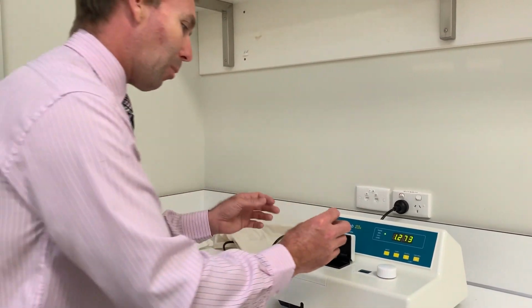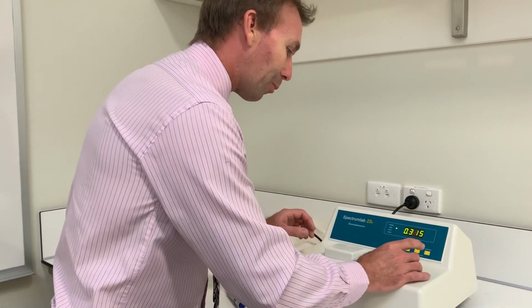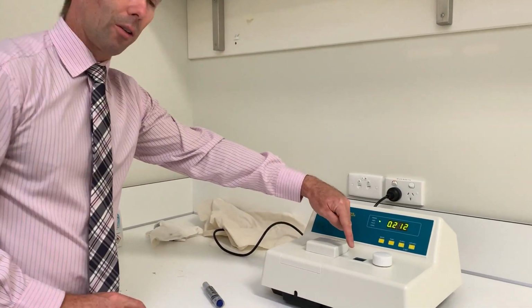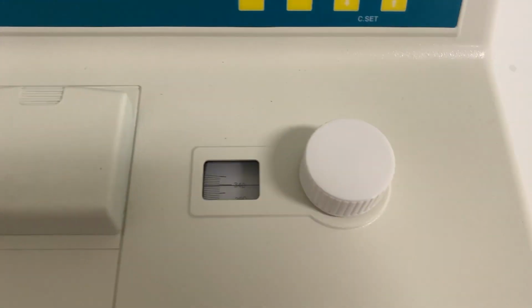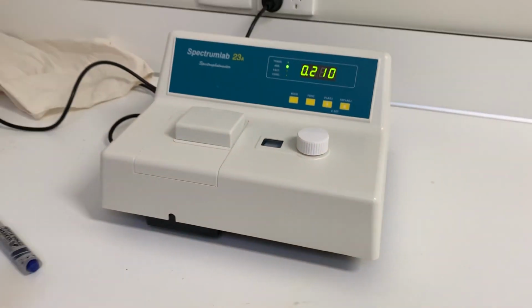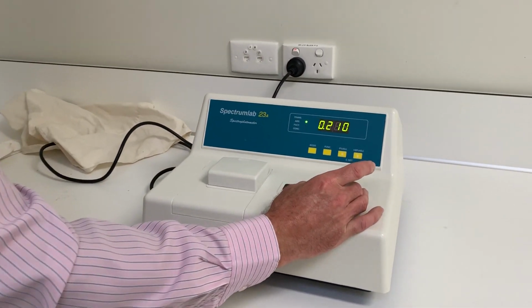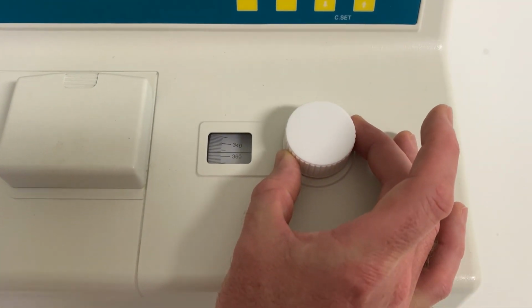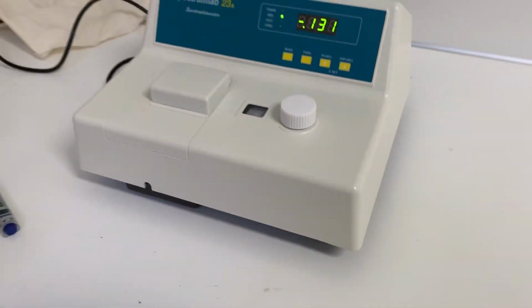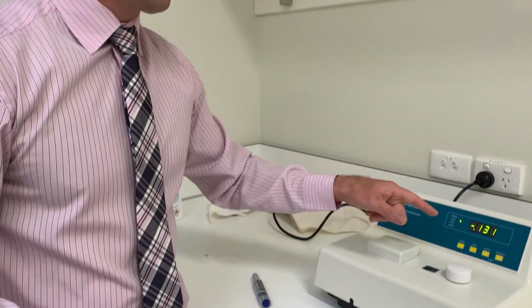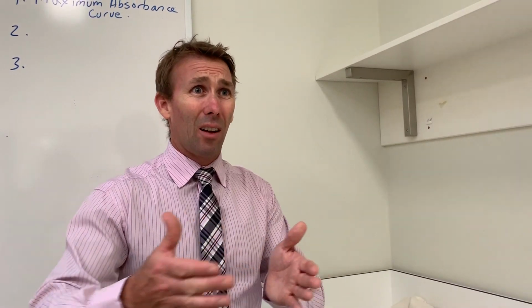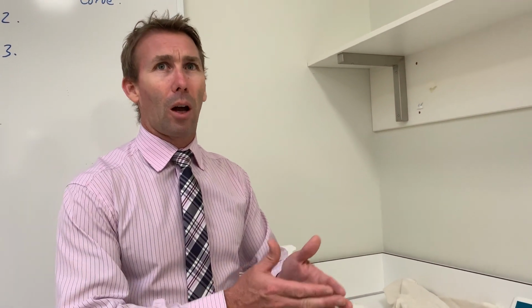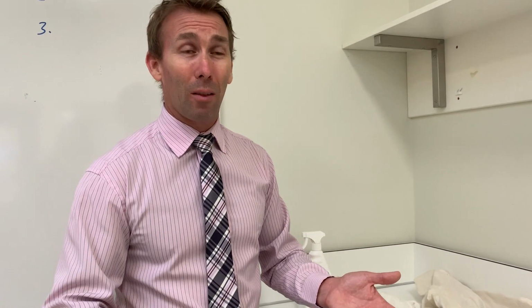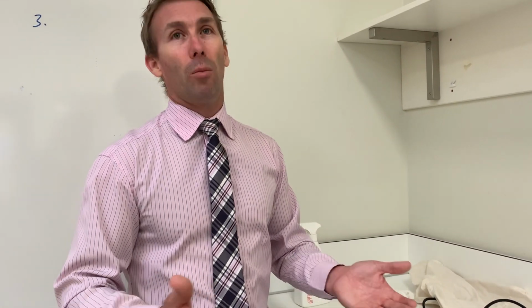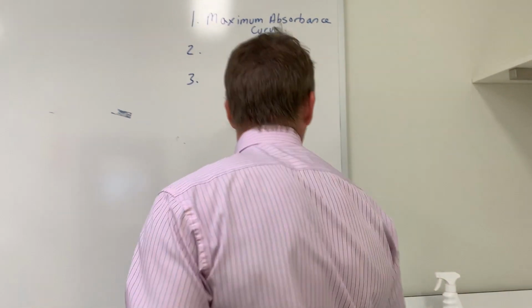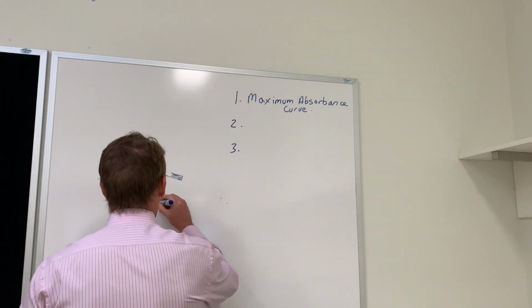So now, assume I'm putting my sample back in after blanking it, and what I want to do is get a reading, and if you just capture there that 340 nanometers, so I'm starting from the very first reading. And then what I would do is dial this up now to say 350 or 360, and I would repeat that process and repeat that process, and what I'll end up with is a reading at every wavelength, and it's up to you whether you want to go up in 10 nanometers at a time or 20 nanometers. Obviously going up in 10 would be more accurate, but also more time consuming as well. So you'll end up with a curve that will look something like this.